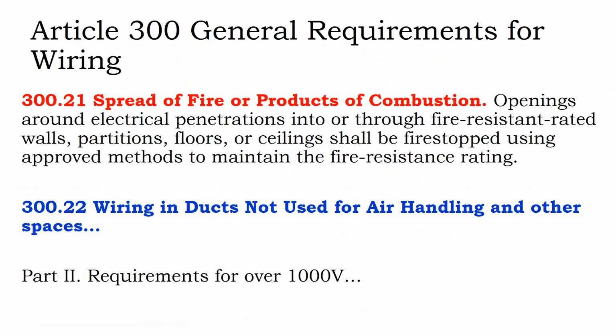Openings around electrical penetrations into or through fire-resistant rated walls, partitions, floors, or ceilings shall be fire stopped using approved methods to maintain the fire resistance rating. So if you're penetrating through a firewall, you may need to use additional sealant at that point of penetration with a higher fire rating, so that you don't void the fire rating of the wall.